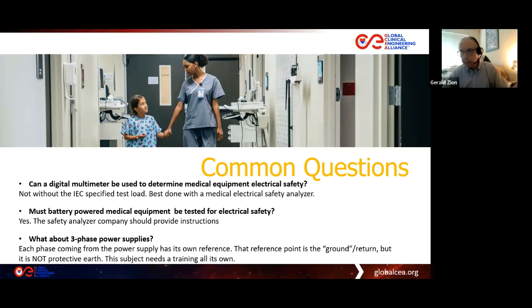There are many manufacturers of electrical safety analyzers specifically designed for the purpose of doing electromedical testing, and so you should use one of those. The medical electrical safety analyzer manufacturer will provide you with the proper way of doing the testing and will incorporate the proper test load into their design.